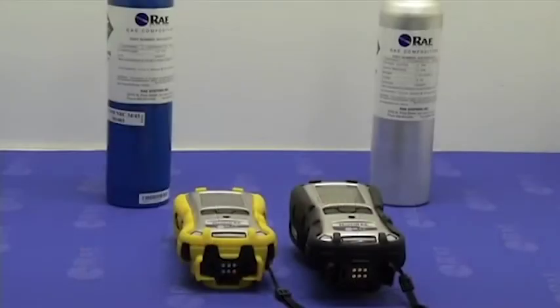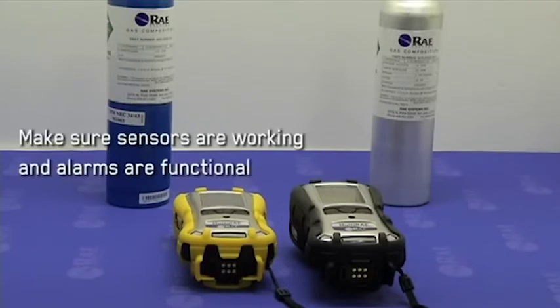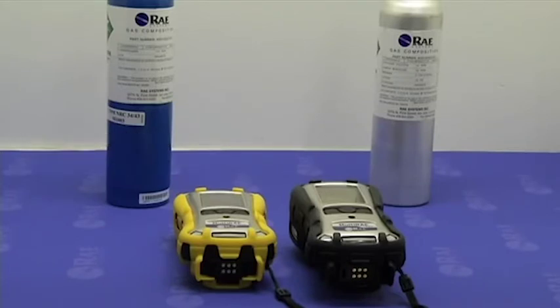Let's get started. RAE Systems recommends that your MultiRAE be exposed to periodic bump testing in accordance with national and regional regulations. The purpose of the bump test is to make sure that the sensors are working and the alarms are functional. A bump test is performed on the MultiRAE by exposing the instrument to test gas in a concentration that exceeds the low alarm limits preset on the MultiRAE.